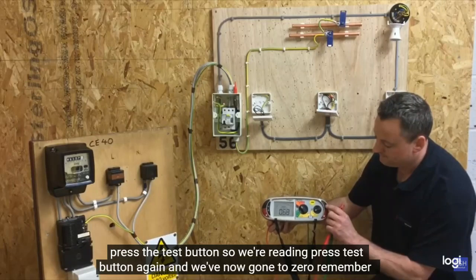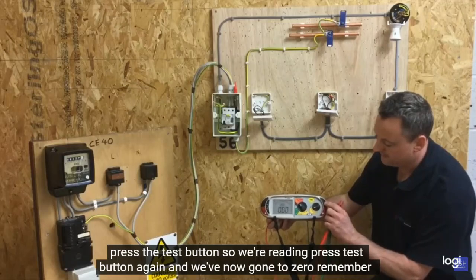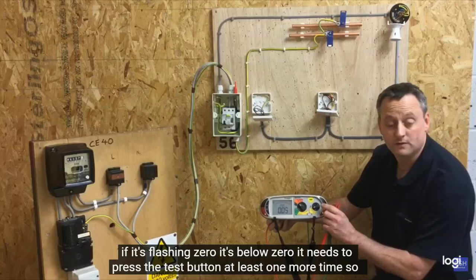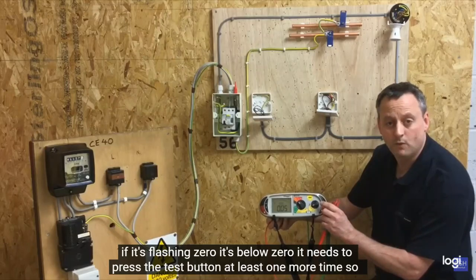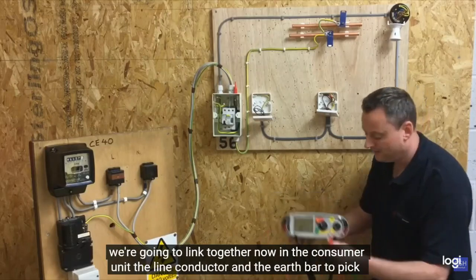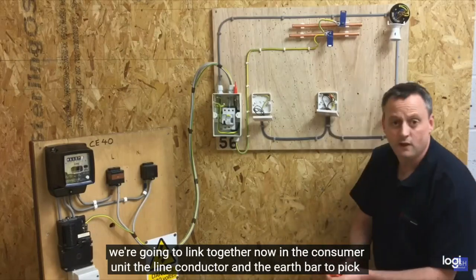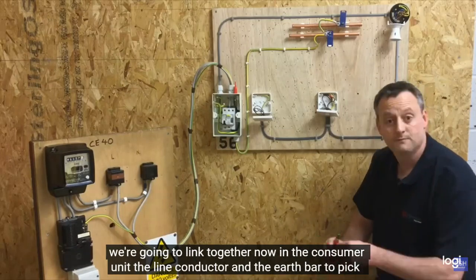So we're going to link together now in the consumer unit the line conductor and the earth bar to pick up the CPC. So we're linking together the line and the earth bar, and we're going to go and test the furthest point on the circuit, which believe it or not is the lighting point.